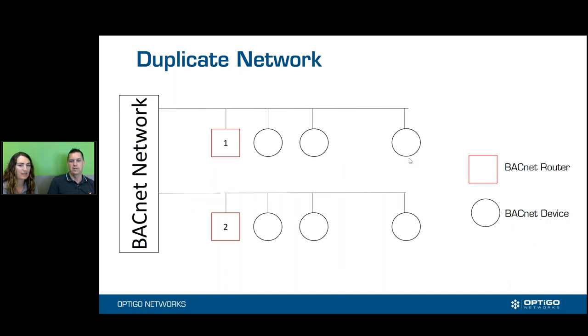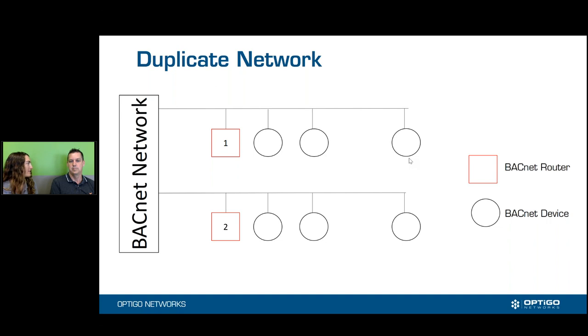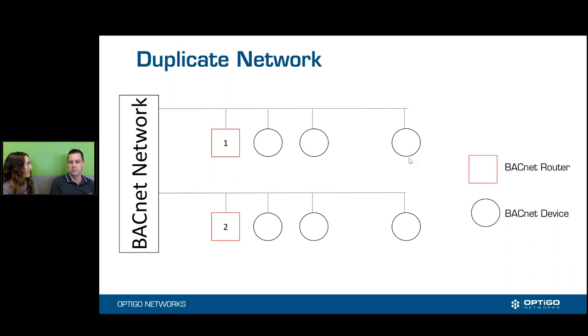This is the network we're looking for. That looks much nicer — no big red X. So basically we've reconfigured it so that router number two is talking to different devices on a different network. Router number one is talking to who it's supposed to based on your drawings, and router number two is connected to who it's supposed to on its drawings, and the two do not cross. Those devices that were probably offline are now back online and we're running well. Now your graphics are going to work and everything's doing exactly what it's supposed to.